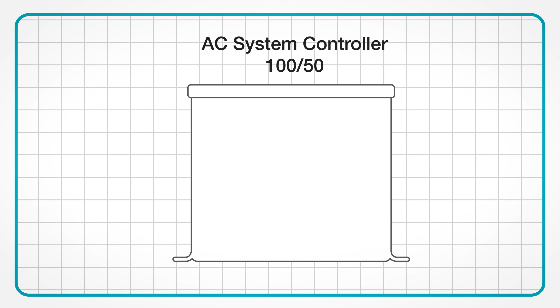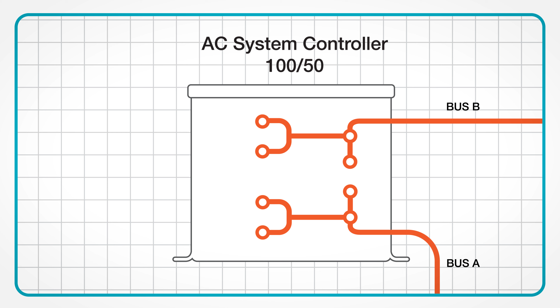There's no setup on this unit, no configuring, it's all pre-done. I'd like to go through some scenarios of what might be available power-wise and how the unit selects between those sources, and what that means for the available power on board the boat. Because we may want to use more than one source at a time, the vessel is split into 2 different power groups, which I'll call Bus A and Bus B. We have 4 sources available: port shore power, port generator, starboard shore power, and starboard generator. So what I'm going to go through is how we select between those and what that means for the power on board the vessel.